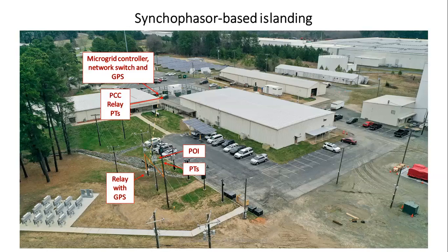So for those of you who might not have seen this before, this is essentially how we do the testing, right? You can see this is our microgrid yard. You can see the point of interconnection. All of the testing we have done was opening this POI. The source side of the POI has PTs, and they are tied to the relay with GPS. Now, we could have had this in the substation or anywhere else. It would have been more or less the same results, just a longer fiber, but it's the speed of light, so it should be the same, right?